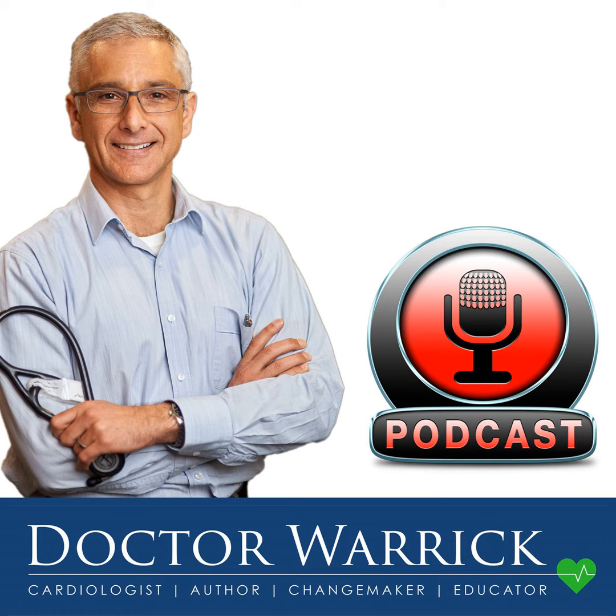I mentioned intravascular ultrasound is an ultrasound probe down the artery, and it uses 20 to 40 megahertz to image the artery. This is in contrast to the probe that we put on the outside of the chest, which has to penetrate at least 10 centimeters, sometimes 15 centimeters, to get a good view. We use 3 to 5 megahertz for that. So the higher the megahertz, the less the penetration, but the better the resolution. So 20 to 40 megahertz is pretty impressive.